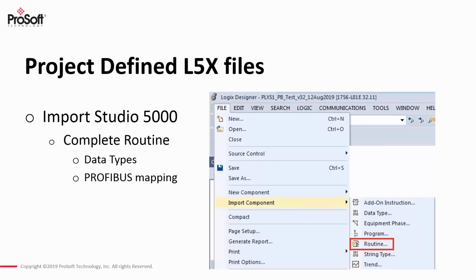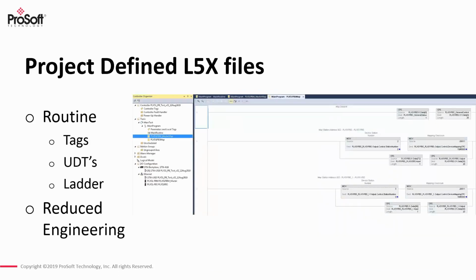So you would go ahead and click on the File menu, Import Component, and then you would select a routine. This goes ahead and brings in all of your data types, your Profibus mapping for each of the slave devices that's configured on the network. And it goes ahead and builds a custom ladder routine based on your configuration that you've set up for the Profibus network, and goes ahead and copies that information over for you into controller tags that are predefined based on this L5X import. So really the benefit of this is just reducing the overall engineering time.